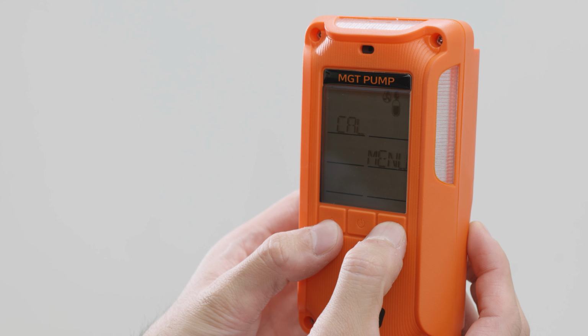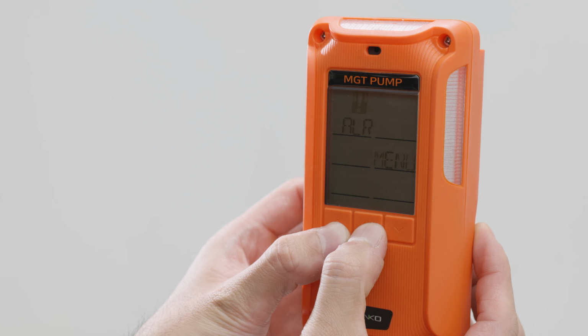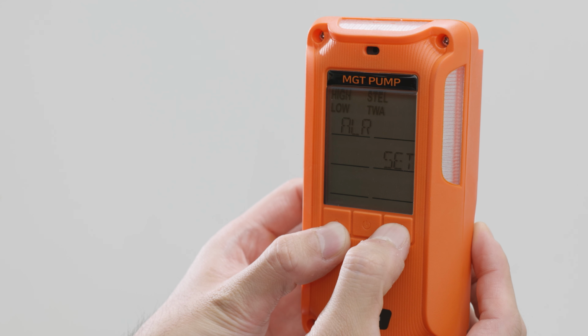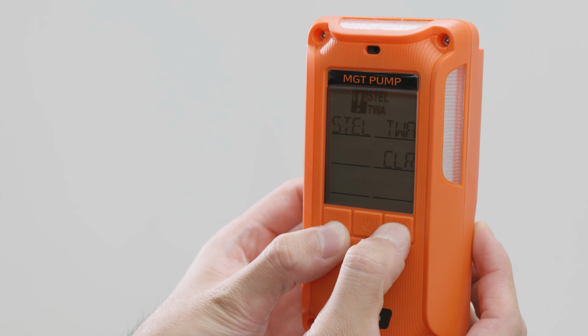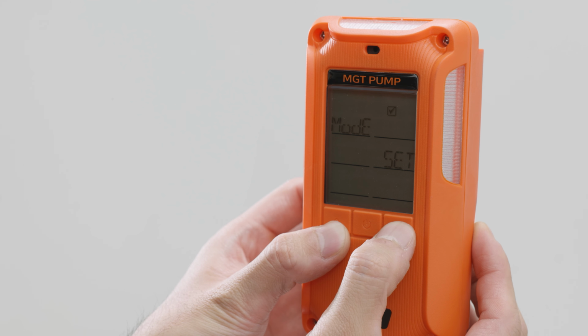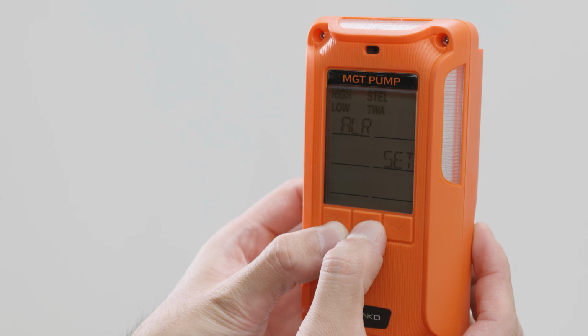In setting mode, select ALR menu, then press the select button to enter the alarm settings. This screen displays 4 options: ALR set, min-max CLR, STEL/TWA CLR, and mode set. Use the up and down buttons to move between options, and press the select button to confirm.